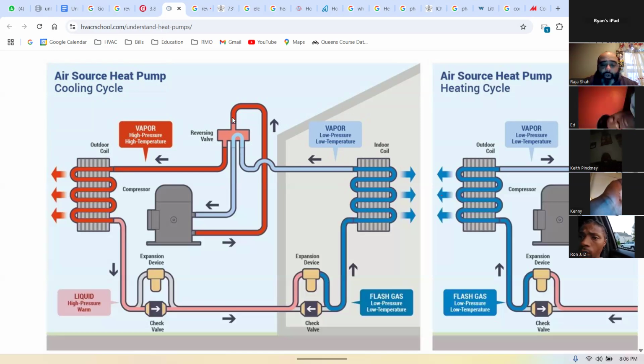All right, so if we got too little subcooling, low subcooling generally indicates not enough refrigerant in the condenser.